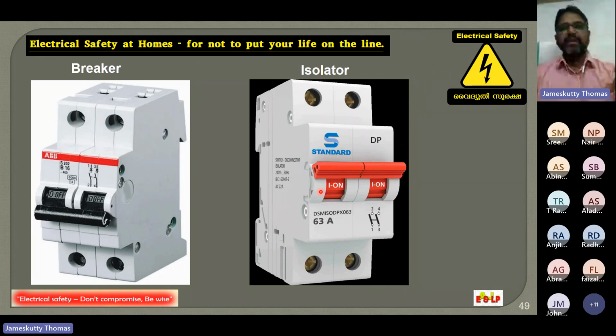If a 10 ampere current passes through a 5 ampere switch, what will happen? It will be burned. Likewise, this isolator will also be burned. So never allow replacing a circuit breaker with an isolator. It will not give protection. The purpose of an isolator is entirely different.